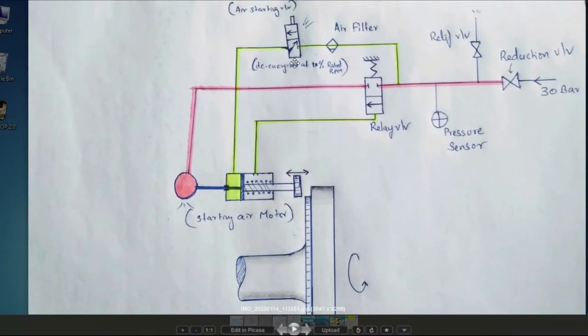So here there is a solenoid valve. This one de-energizes at 10% of the rated RPM. So when generator reaches 10% of the rated RPM, this one de-energizes, and this one will be in this position.